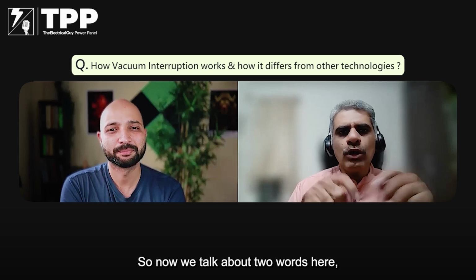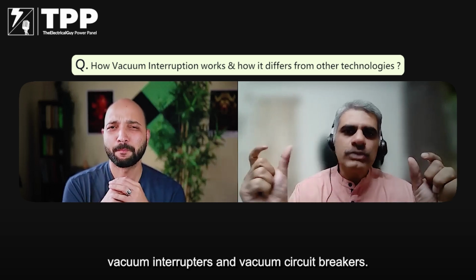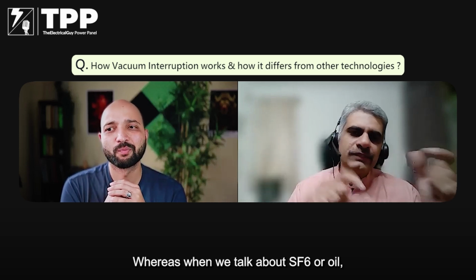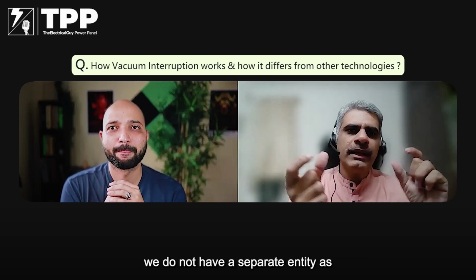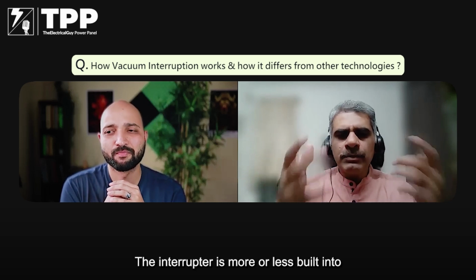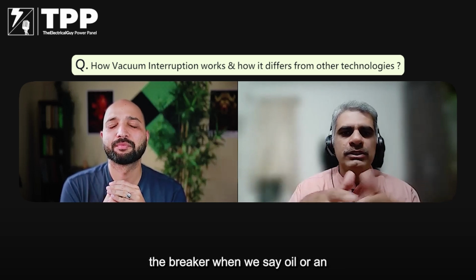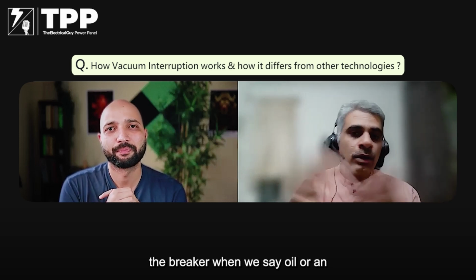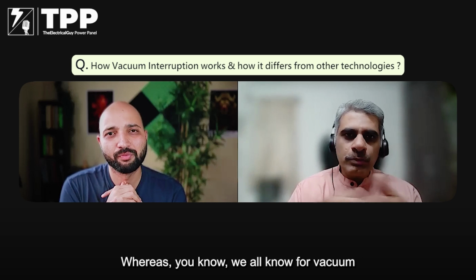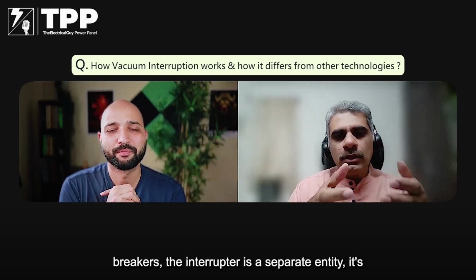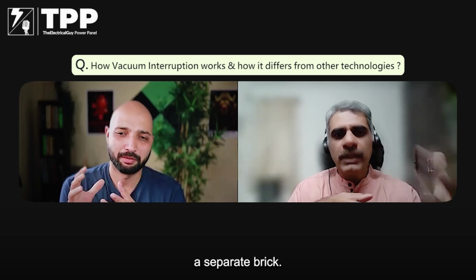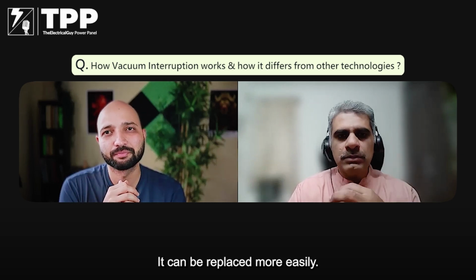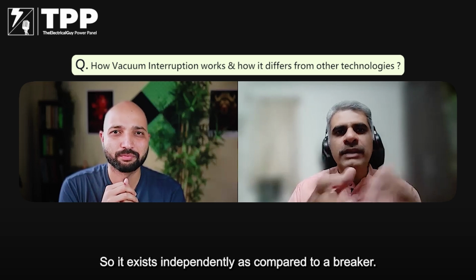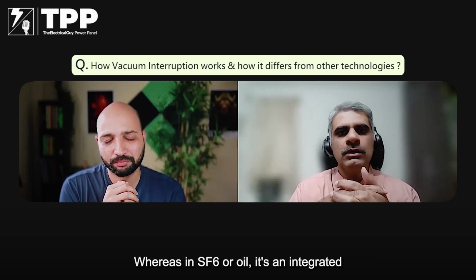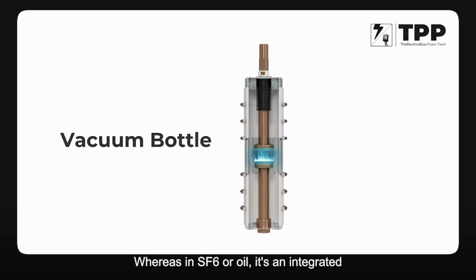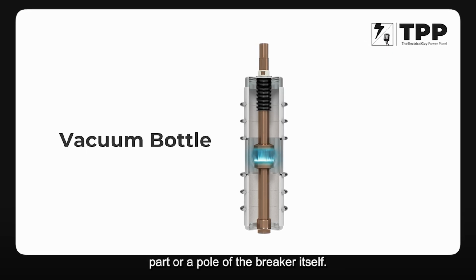Now we talk about two terms here: vacuum interrupters and vacuum circuit breakers. Whereas when we talk about SF6 or oil, we do not have a separate entity as an interrupter. The interrupter is more or less built into the breaker when we call it an oil or an SF6 breaker. For vacuum breakers, the interrupter is a separate entity, a separate brick. It can be replaced more easily. So it exists independently of the breaker, whereas in SF6 or oil, it's an integrated part or a pole of the breaker itself.